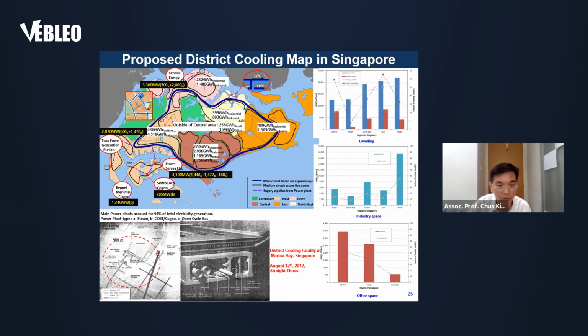Now, with this new paradigm change or this game-changing technology that we introduced, either the membrane or the super absorbent at your air handling unit, the chill water temperature can now run at about 15 to 18 degrees, right? Not at 5 degrees. So in other words, 15 to 18 degrees compared to previously 5 to 6, the insulation of your pipe no longer needs to be so thick and so bulky, right? It can be much thinner insulation that's required at your chill water pipe, right? But it's running for hundreds and hundreds of kilometers, and that will save you a lot of energy, besides energy, also heat losses pertaining to energy, but also the costs as well, right? The cost to insulate the chill water pipes, right? So that is another very big plus, right? Both operational costs in terms of energy saving, as well as capital cost in terms of using less material for insulation.